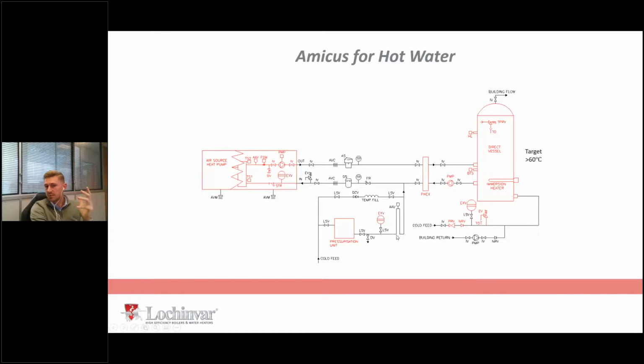Air source heat pumps have limitations, and that limitation is that your maximum flow temperature is probably going to be around 65 degrees from an air source heat pump if you still want it to run efficiently. So the air source heat pump in our case, what we would do is we would flow at 63 degrees centigrade. Now remember, we've got that 5-degree delta T, so we flow in at 63. We return at 58 on the primary.